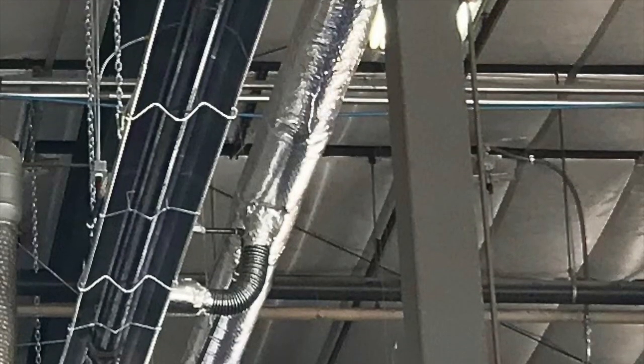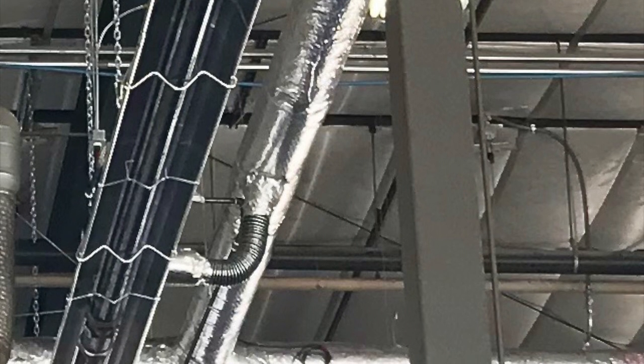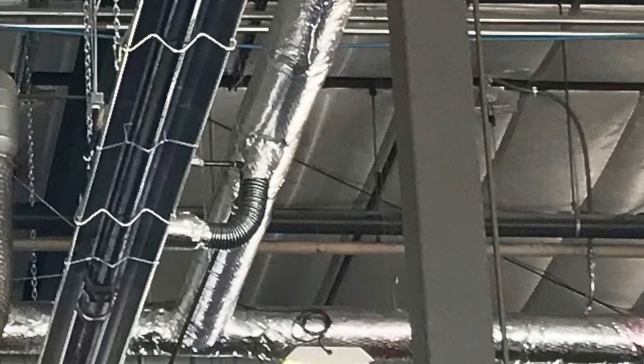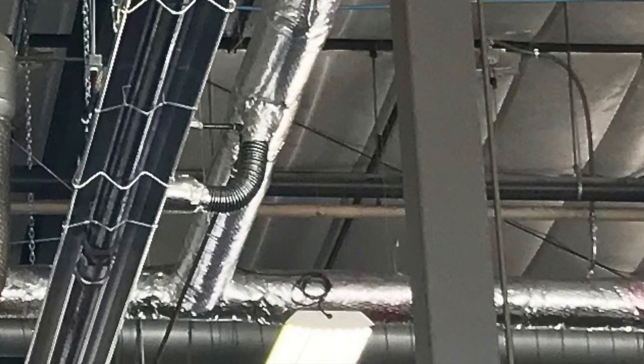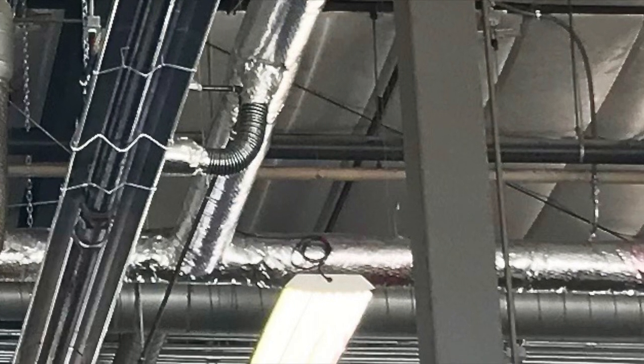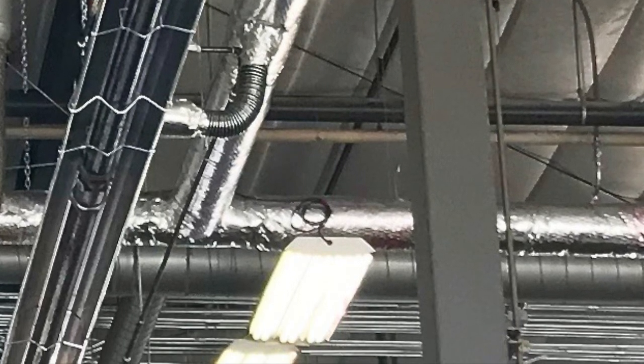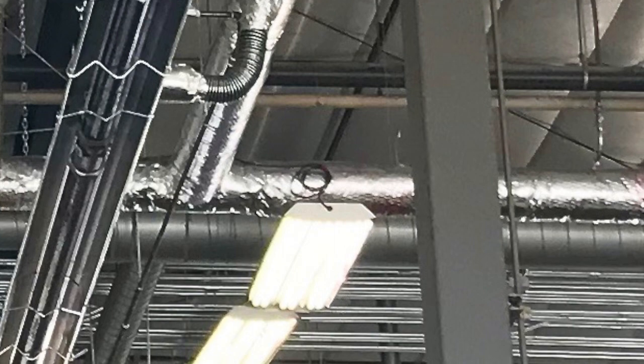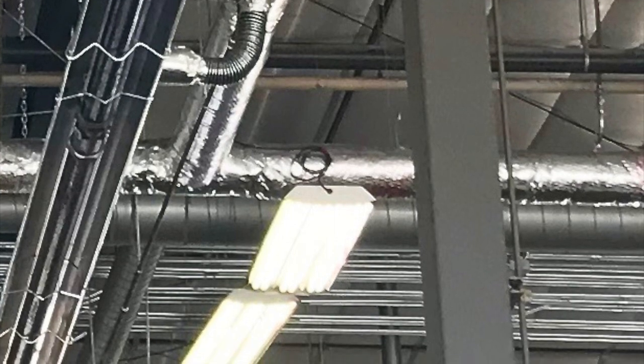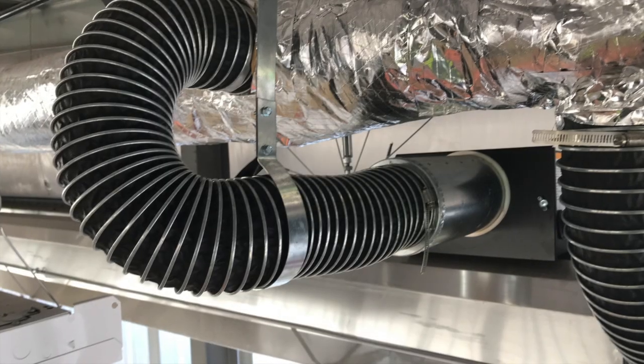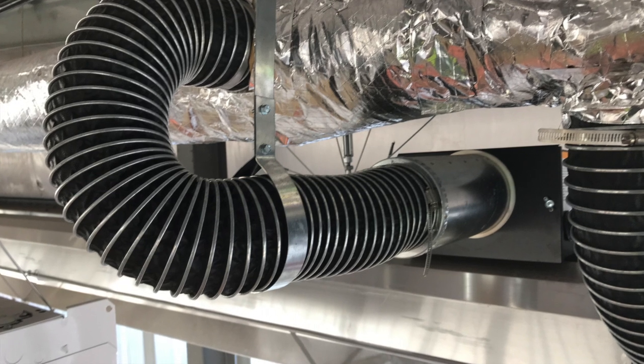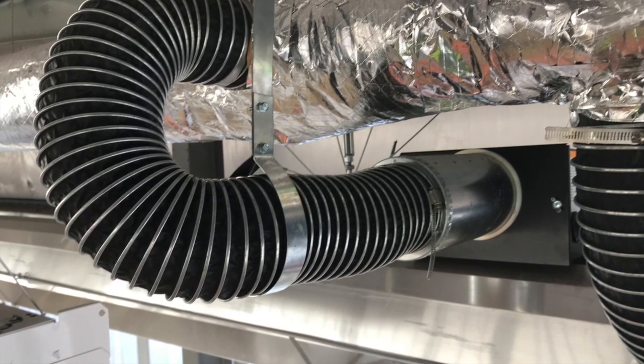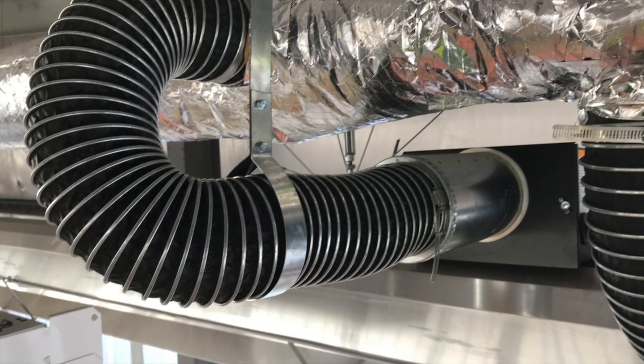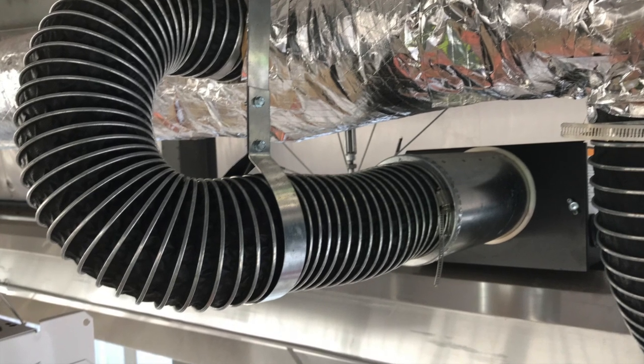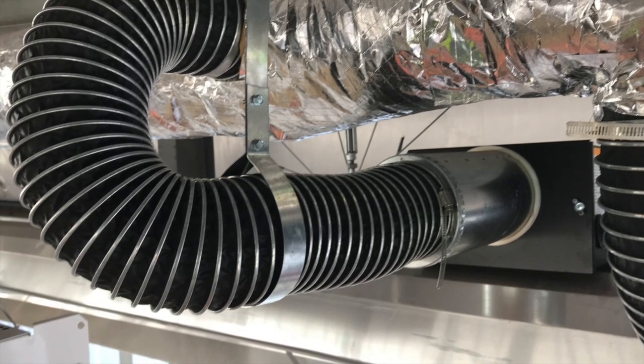Combustion air installation. Having the spiral ductwork 1.5 to 2 feet off center of the heat exchanger, 2 feet above the system, should allow for combustion chamber air flex without the need for a flex duct hanger. Having the spiral ductwork away from the heat exchanger at the same elevation, we will need a hanger on the flex to support the weight of the flex as it can pull on the filter housing at the burner.